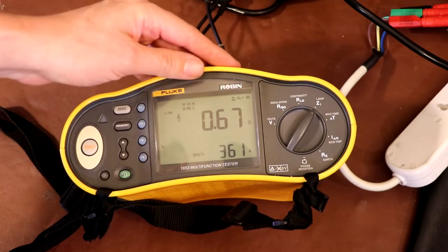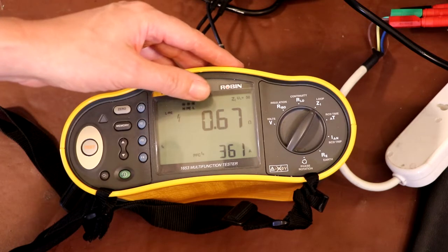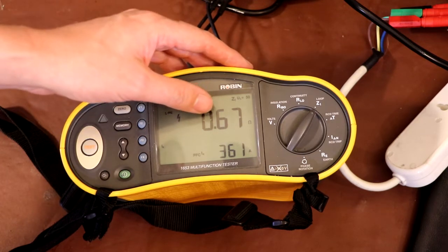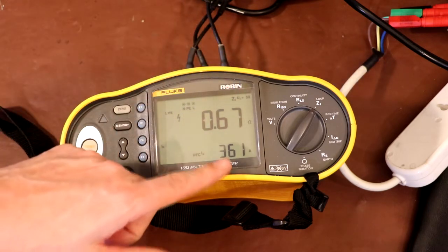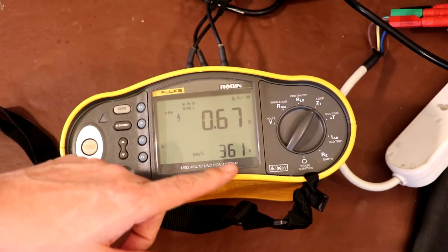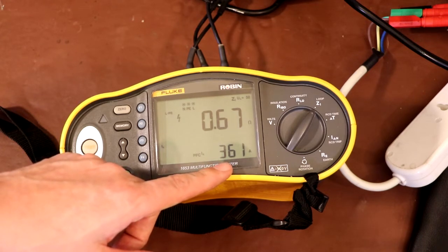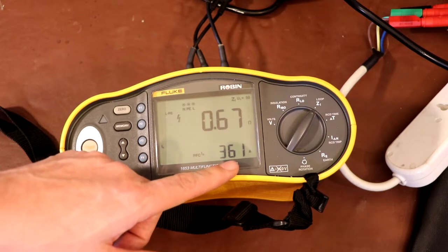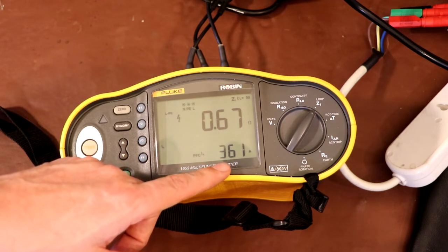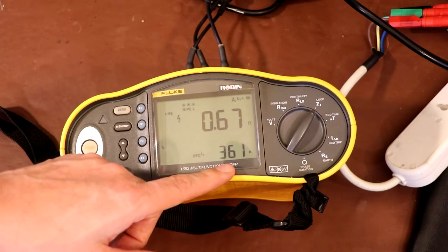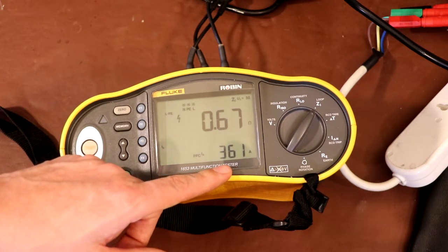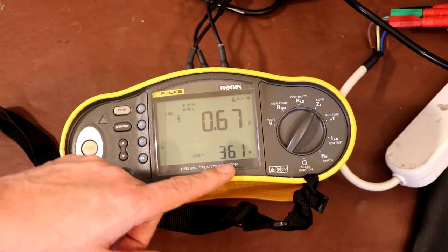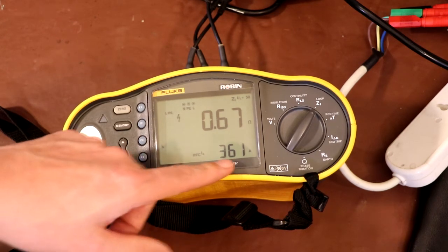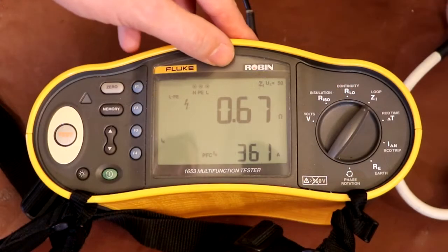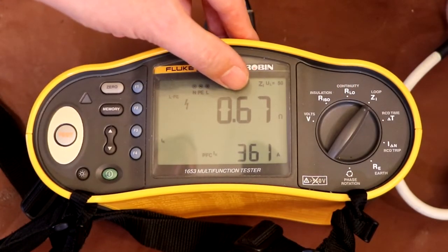So the meter's come back and it's reporting two values. It's saying that the resistance between our live conductor and earth is 0.67 ohms, and based on that resistance it's also measured the supply voltage, and it's saying that the absolute maximum current that we could pull from our installation here in my house is 361 amps. Now of course you couldn't really pull 361 amps, well, you probably could momentarily, but we've got circuit breakers that would trip out eventually, and the house is probably protected by a 100 amp fuse. Of course fuses and circuit breakers don't trip instantly, so for very short times you could probably pull 361 amps quite easily. Anyway, the reading that we're interested in here is 0.67 ohms.